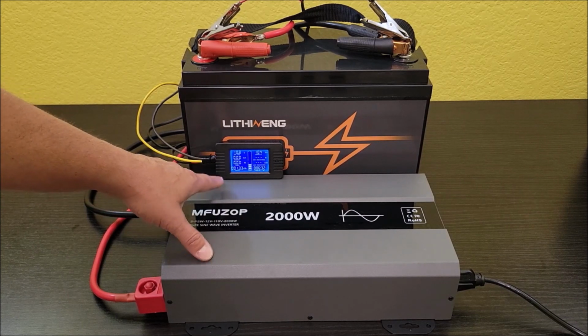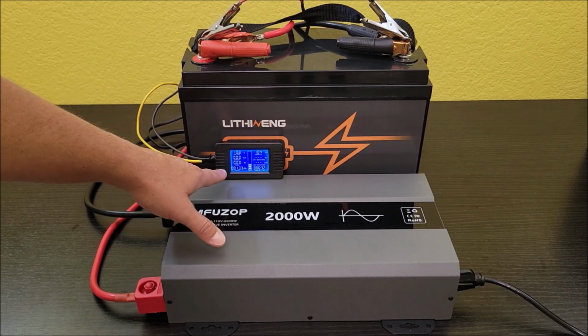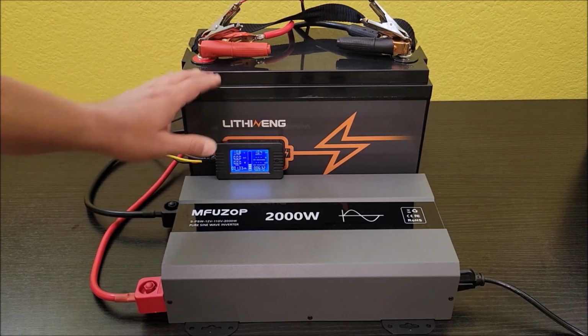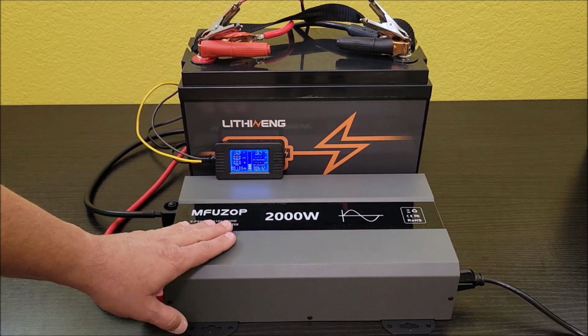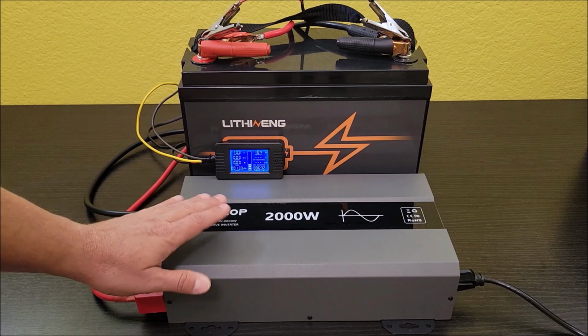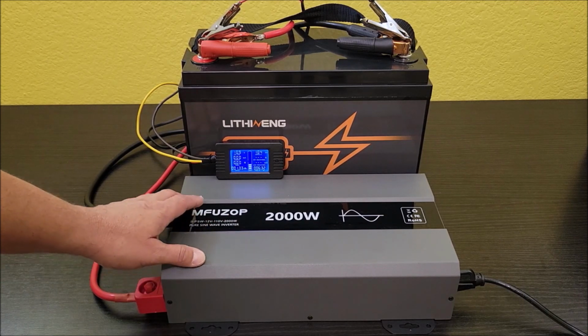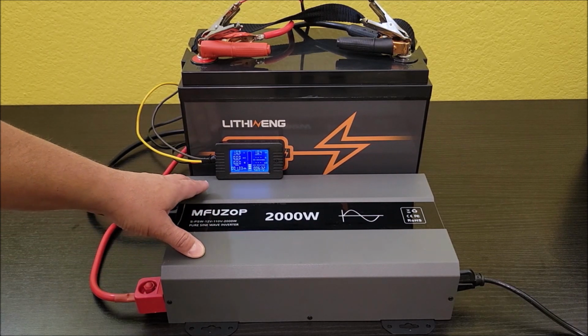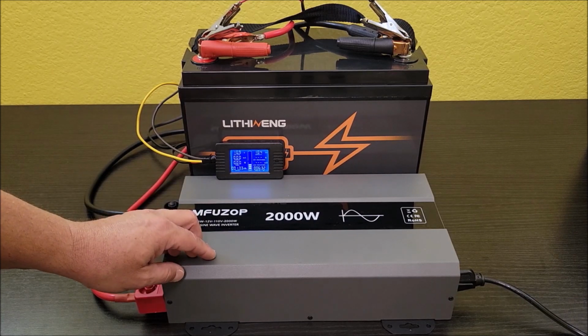So this inverter did drop out. The BMS did not kick off, because as you can see, this is still powered. If the BMS would have kicked off, this would have gone dark. So once the inverter hits 10 volts or less, that's low voltage and it's going to cut off. It starts beeping at 10.5, I think it is, and then it cuts off at 10.